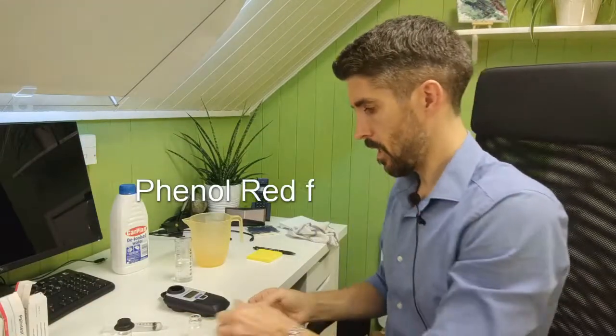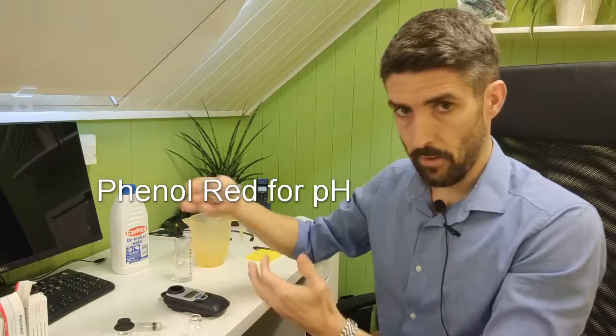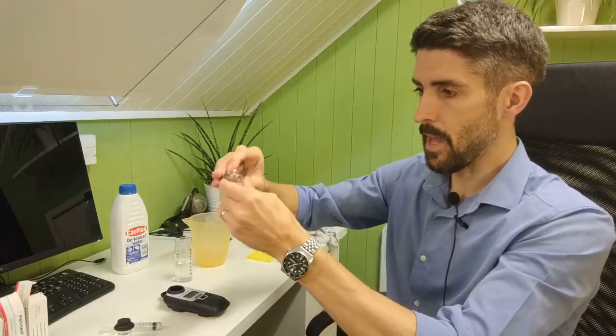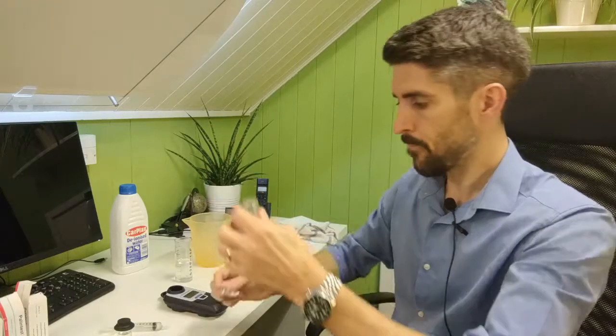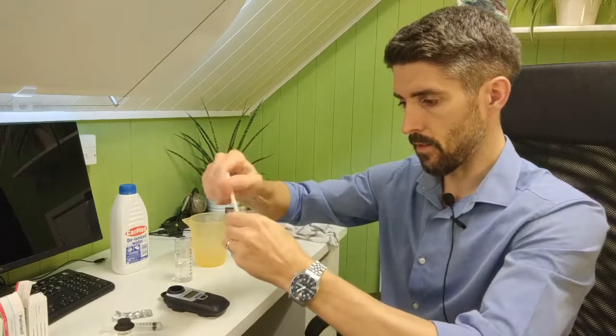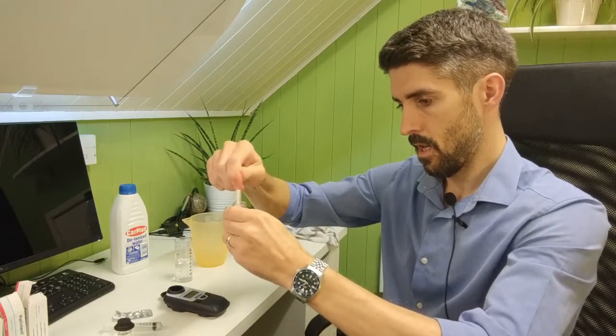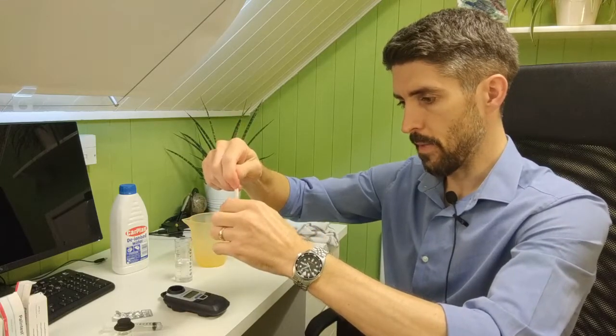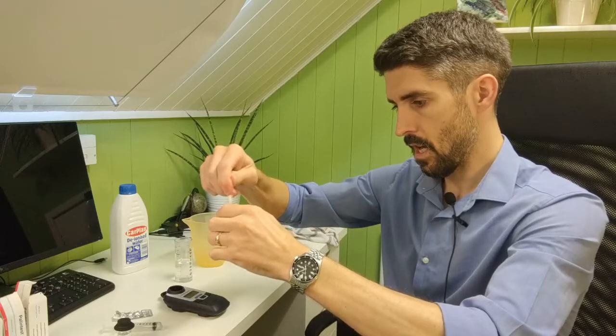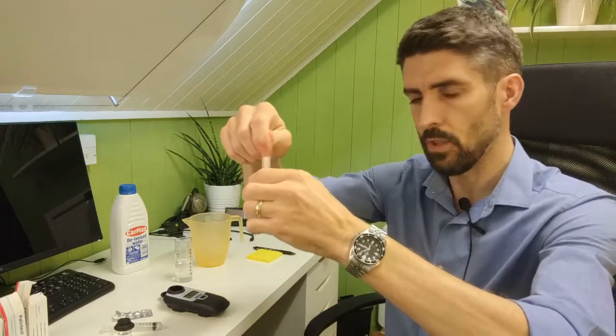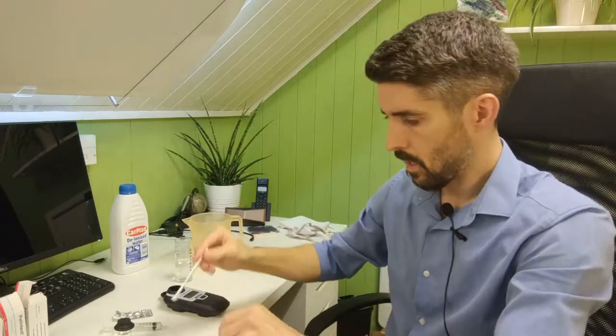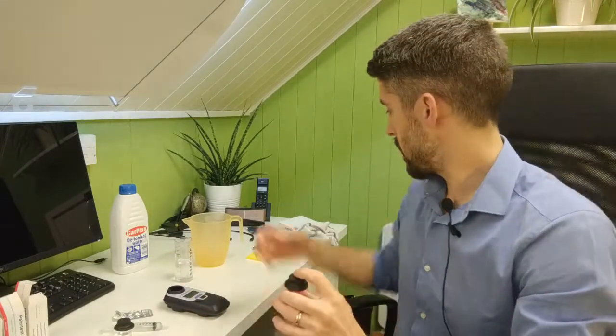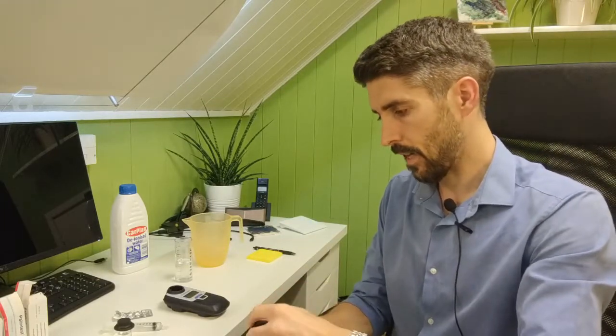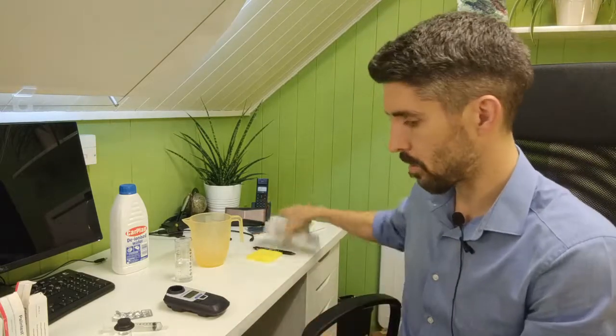And then what you want here is a phenol red tablet. Again, a phenol red tablet for a photometer, not a phenol red tablet for a comparator. Pop that in there without touching the tablet with your fingers, and do crush it up in the usual way. And again, make sure that the tablet fully dissolves. And just before I take the pH, again, make sure everything's clean, make sure everything's dry. And that goes for all of the tests that you do with the photometer. Everything's got to be clean, everything's got to be dry.